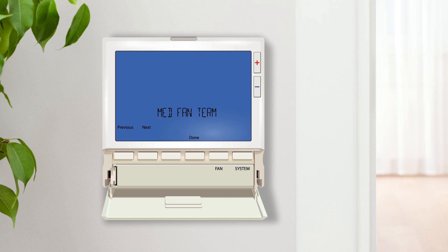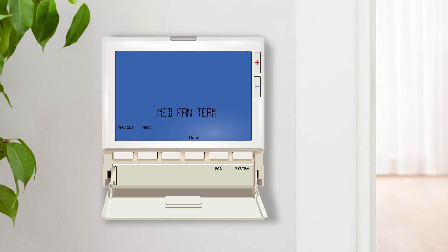Many of the advanced features require the use of an additional terminal for operation. Since all ProOne models have a separate O and B terminal, whichever is not used for the reversing valve can be used for these advanced settings. However, because only one terminal is available, we can only use one advanced setting for each system configuration. This means you must choose between PTAC, three-stage cooling, fresh air and economizer mode.